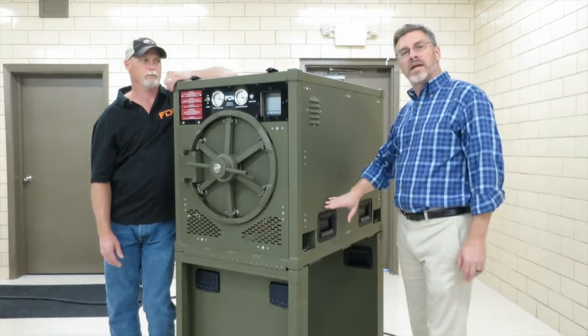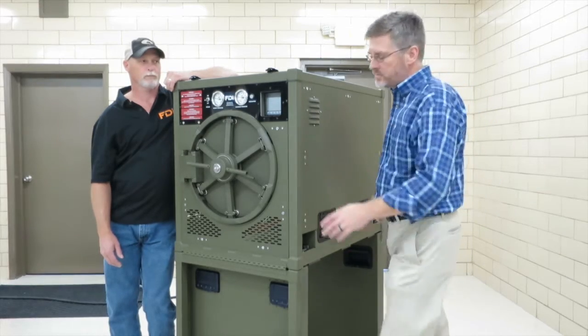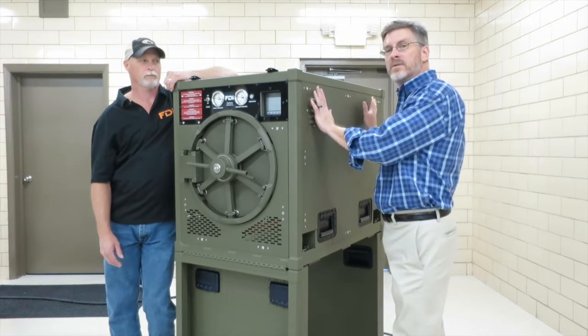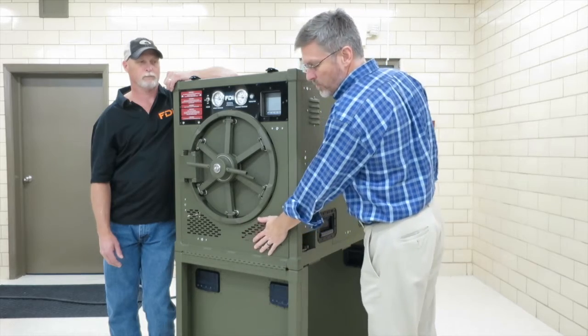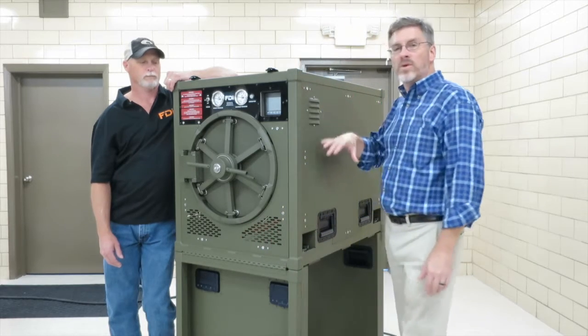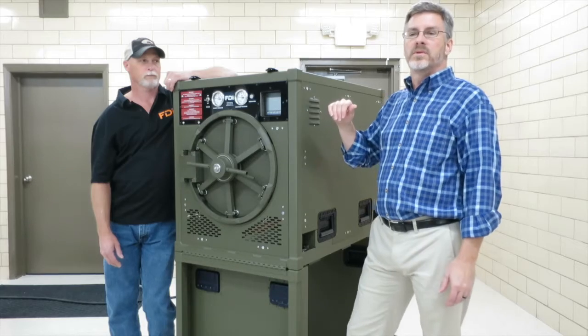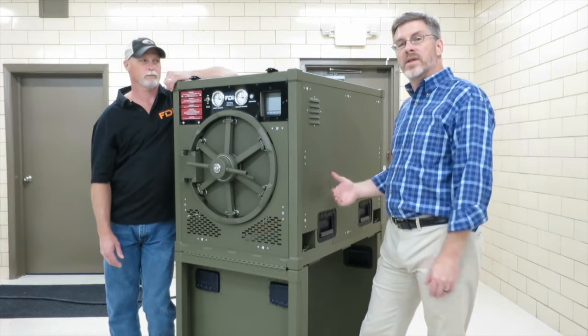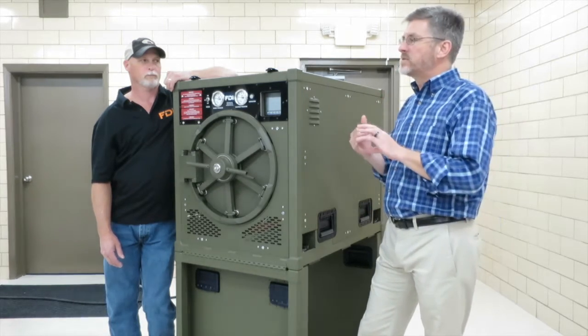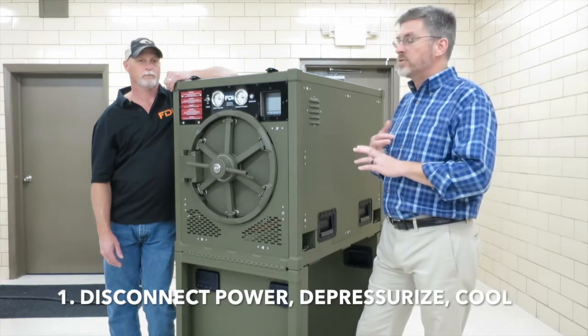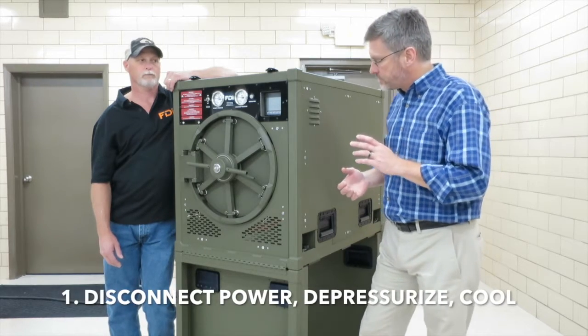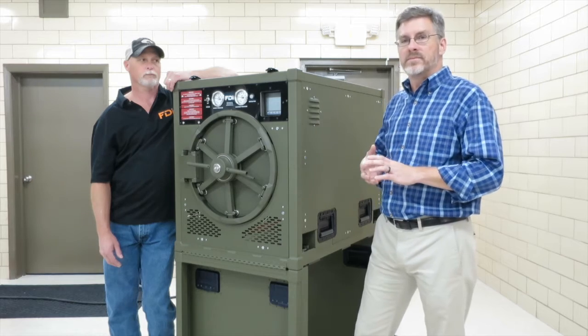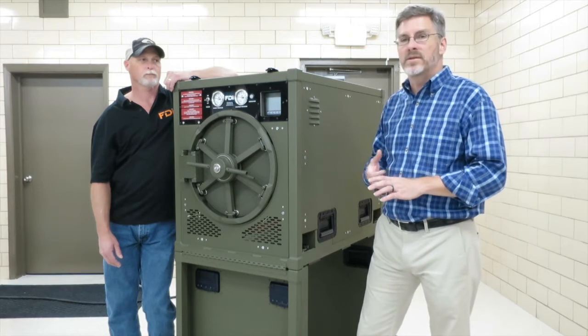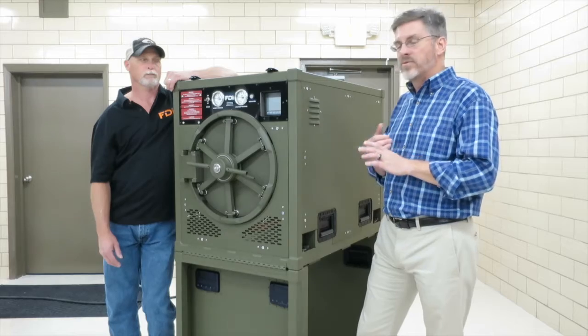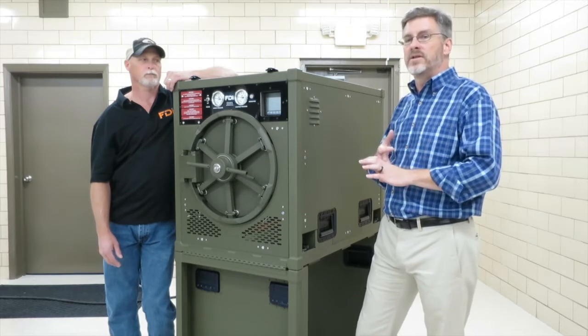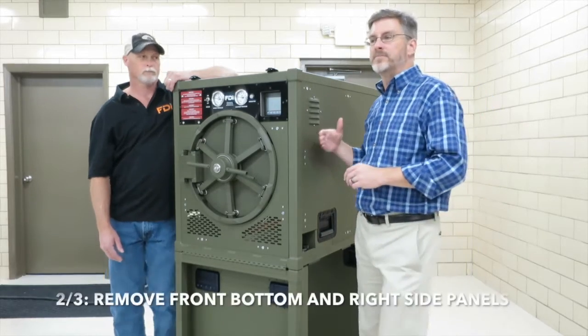This side is where the cables are, so we're going to have to remove this panel, which has the electrical box behind it. We're going to remove the front bottom panel. Just a word on this, we're breaking into plumbing, we're breaking into electrical, so always turn your unit off, make sure it's depressurized, and it could be very hot. The chamber gets really hot, the drain gets hot, and that probe will get hot. So make sure everything's cool, depressurized, and de-energized. So we're going to go ahead and take the panels off right now.